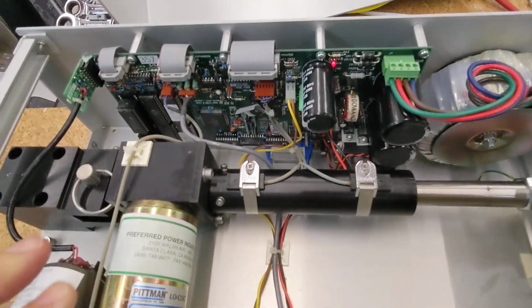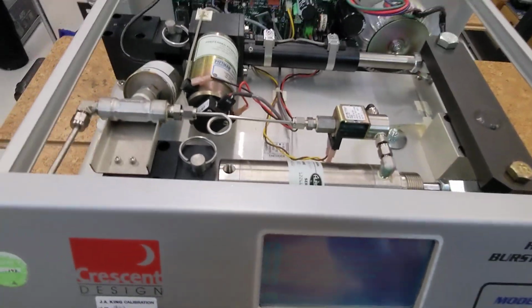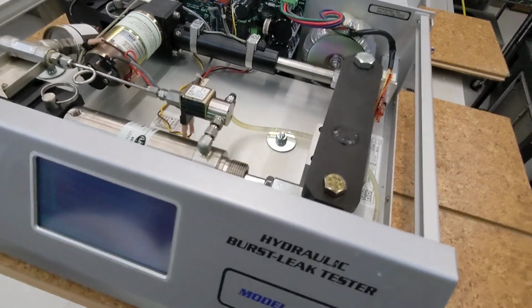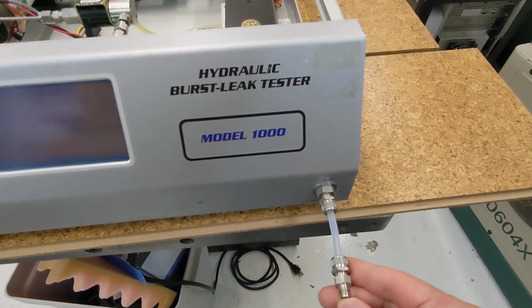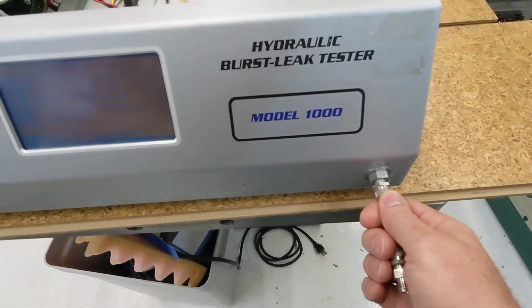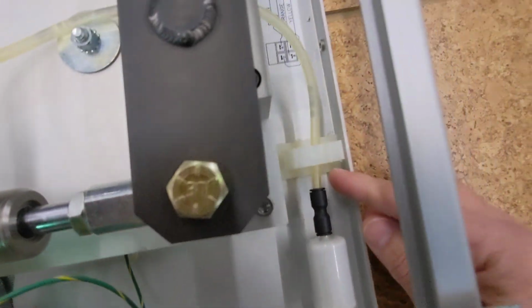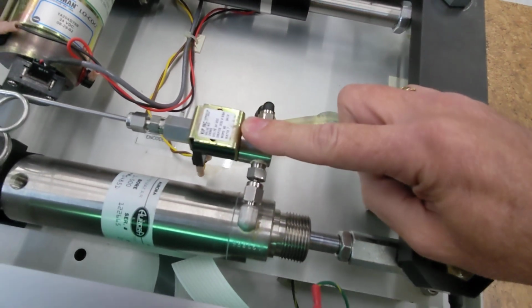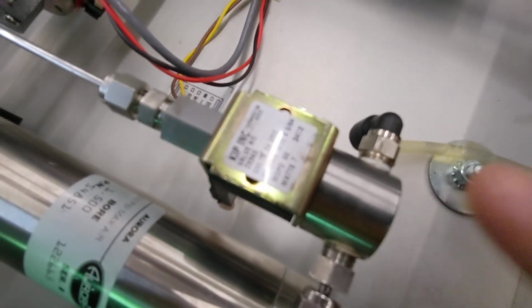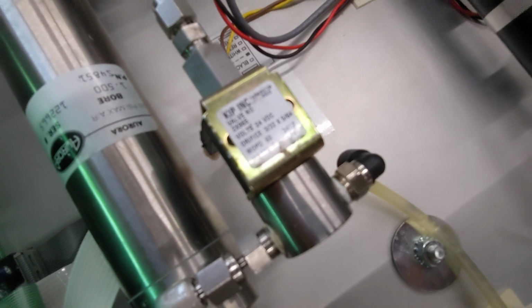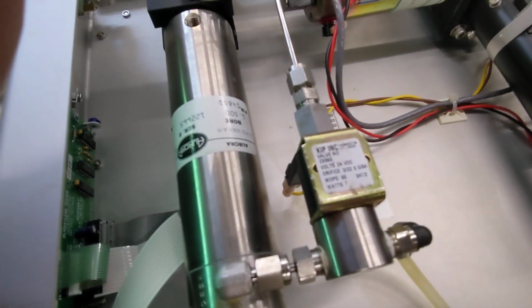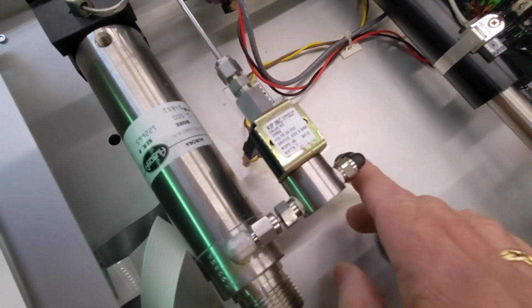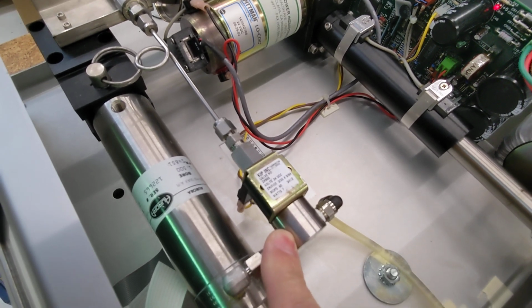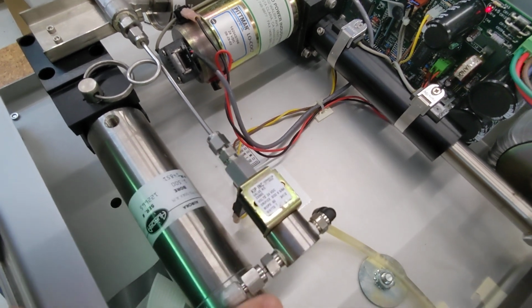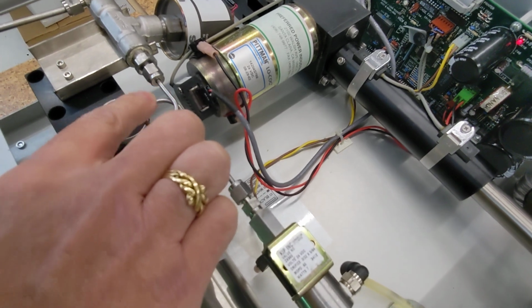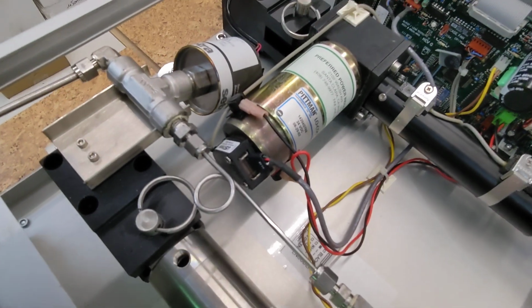Before I get into too much with that stuff, let's talk about how it actually works. The thing that I just knocked off the table is a big bottle, and that's the supply water that comes in here. We bring in some nicely filtered water here, and that goes through a filter again, runs through this tube, up into this valve right here, which is high pressure. The valve is from KIP, so it's a high pressure KIP 24 volt valve. It's going to bring that in and then close off right here. If you notice, it's a three-way valve. There's also another way that this can go out, up through here. There's a little pigtail here to make up for some space if you need it.